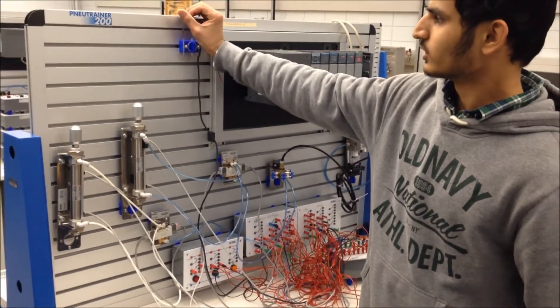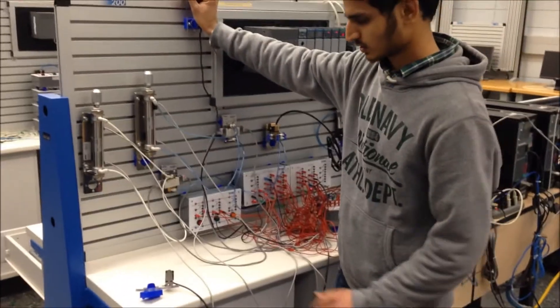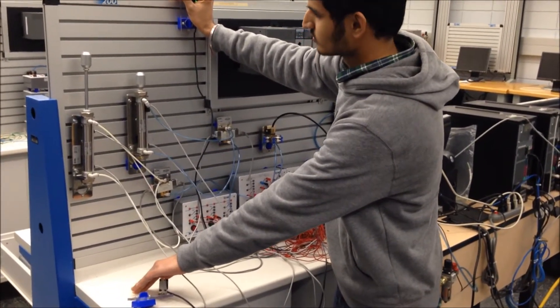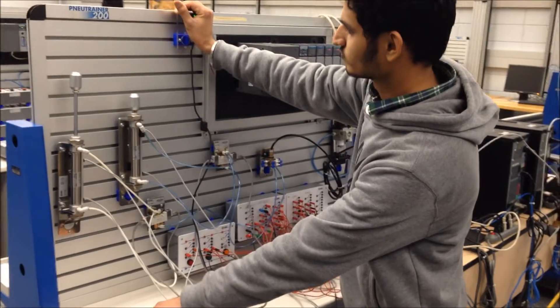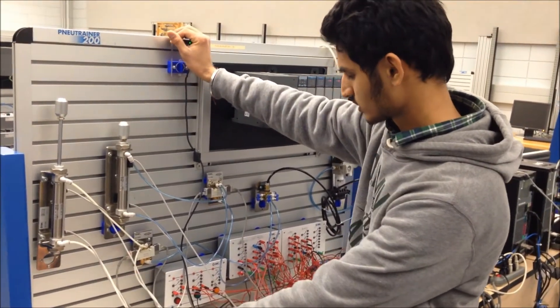It restricts the function of cylinder B. If I place my hand here instead, you can see that only cylinder A extends. This confirms that both photosensors are working.